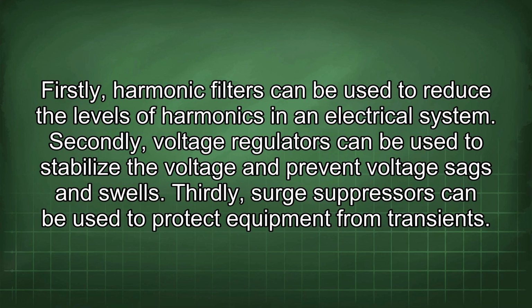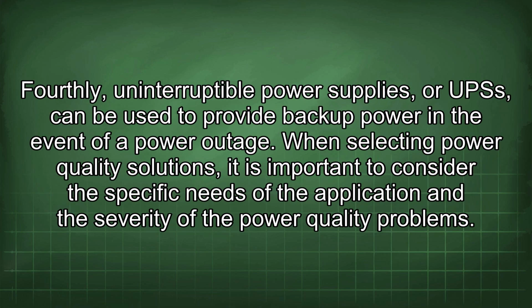Firstly, harmonic filters can be used to reduce the levels of harmonics in an electrical system. Secondly, voltage regulators can be used to stabilize the voltage and prevent voltage sags and swells. Thirdly, surge suppressors can be used to protect equipment from transients. Fourthly, uninterruptible power supplies, or UPSs, can be used to provide backup power in the event of a power outage.